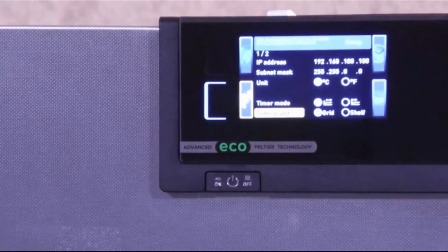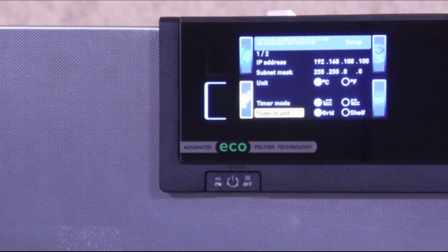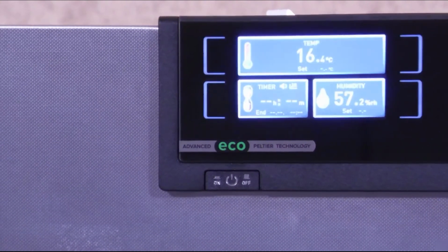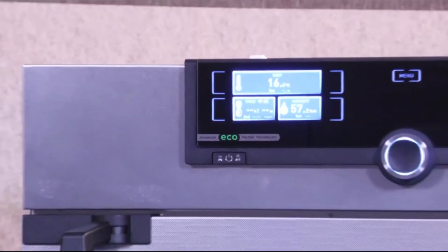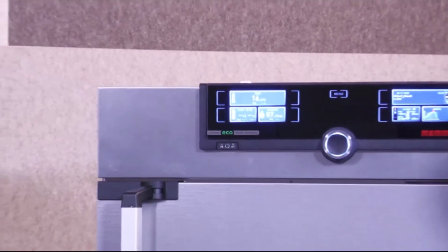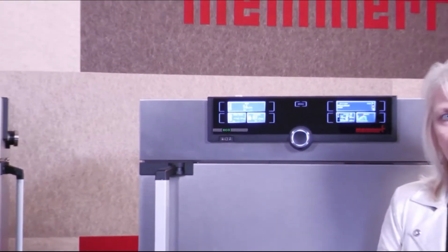Depending on whether you have ordered a grid or a shelf, the calibration will be done in our production at the final test field, because the correct setting on the unit has an influence on the uniformity. So based on this execution, whether it's grids or shelf, we also issue the calibration certificate during the final calibration of our products.